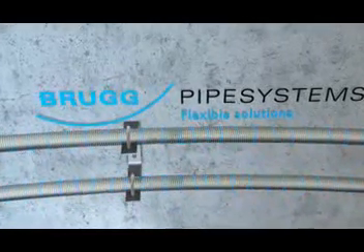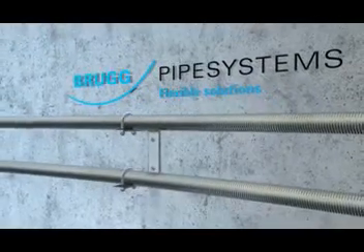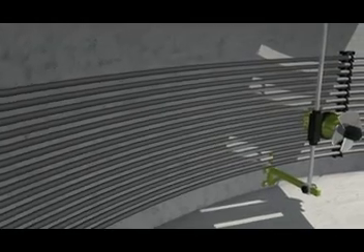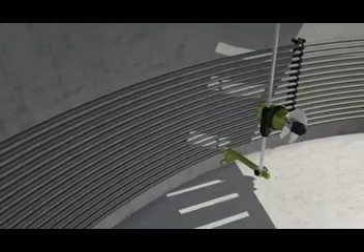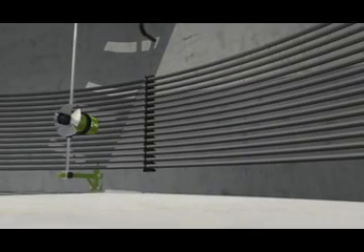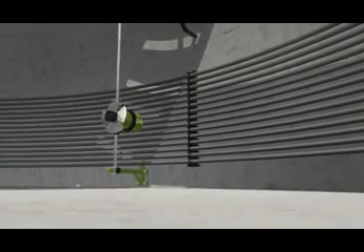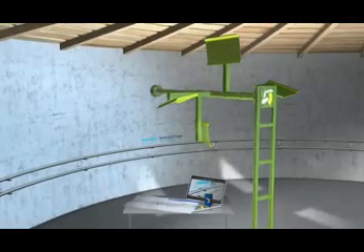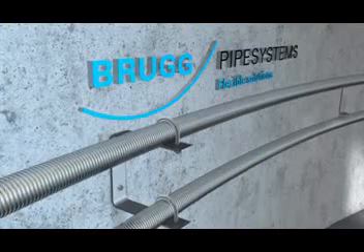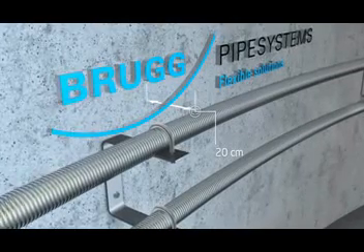Brugg offers an ideal and especially safe heat transfer system incorporating a stainless steel corrugated pipe. Its design is in contrast to the smooth-walled polymer-based pipes used in other heating systems, which have well-known diffusion problems leading to less efficient heat transfer. The Brugg fermenter heating system incorporates a DN-50 corrugated pipe installed on the fermenter wall and fixed at intervals of 20 centimeters.